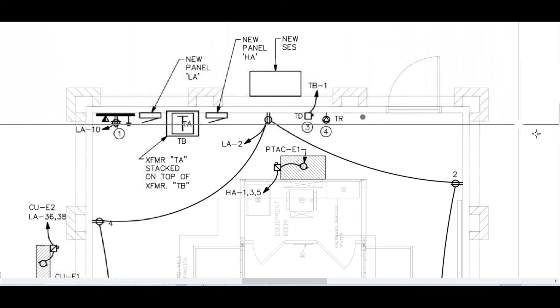Notice how I listed 2 3-inch Myers hubs, 2 3-inch LBs. Red Rhino Estimating Software has all these products in it with pricing and labor: 2 4-inch core drills—you have to oversize the core drill for a 3-inch conduit to the outer diameter, so close is a 4-inch core drill—4-inch core drill patch, and then transformer wall bracket for that 75 kVA transformer. Okay, so that's it for this video.